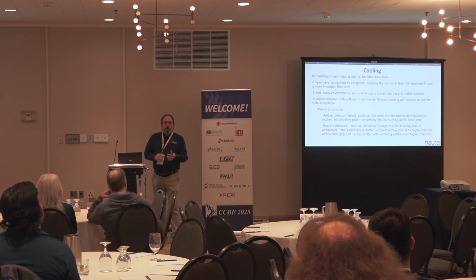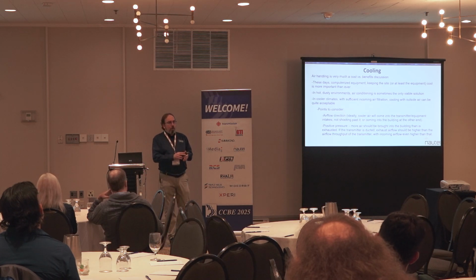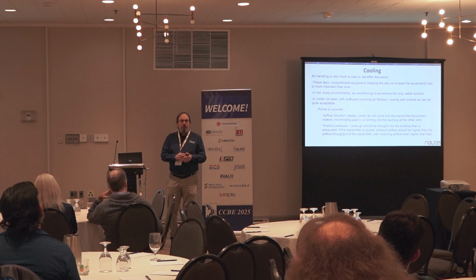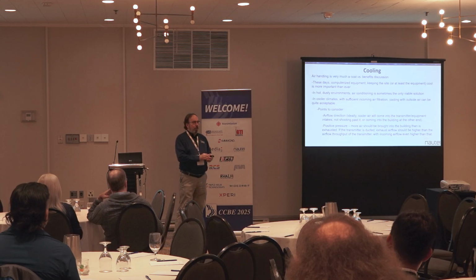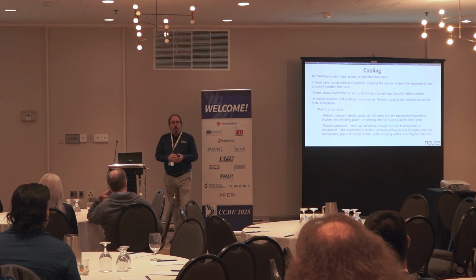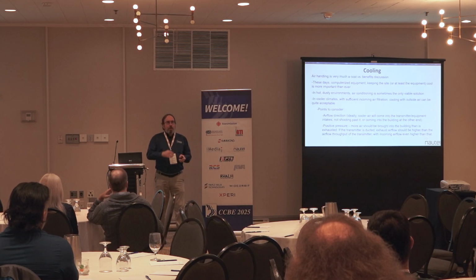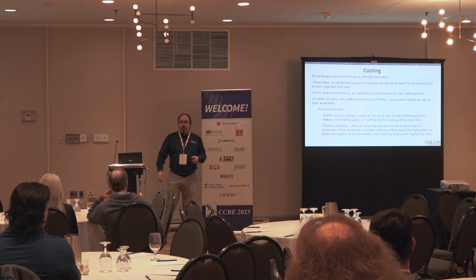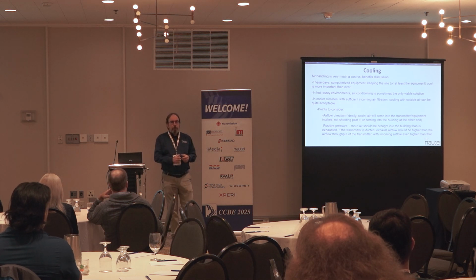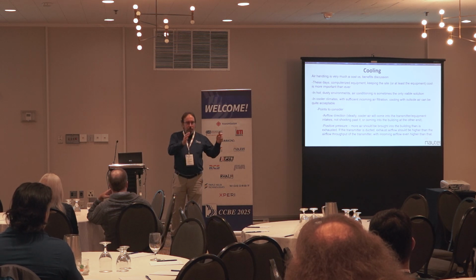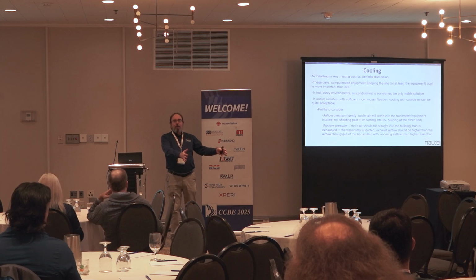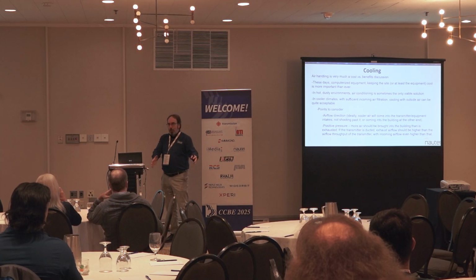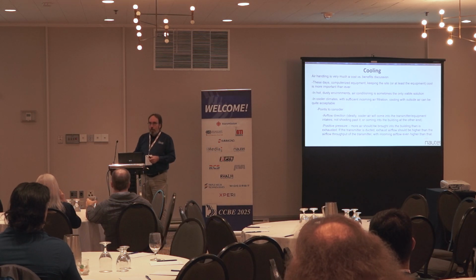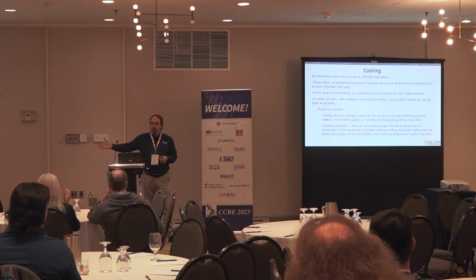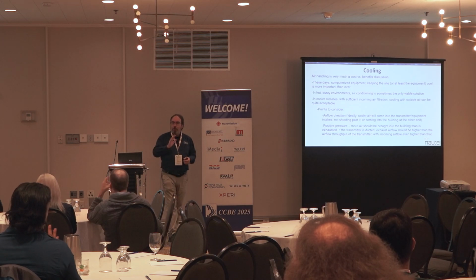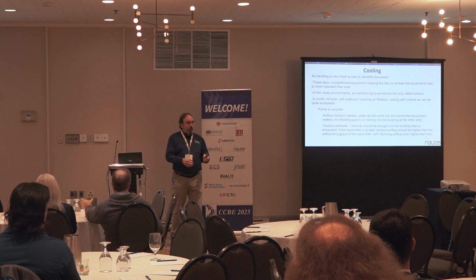Here's the funny thing. A guy working for one of our competitors, or really a complementary company since we don't build liquid cooled and they do, used to run around telling people liquid cooling requires zero maintenance. Horse pucky. You're putting a heat exchanger outside, and I promise you, at least once or twice a year, you're going to want to go out and clean the crap out of the coils on the heat exchanger, because the efficiency will go to pot and things start getting toasty.